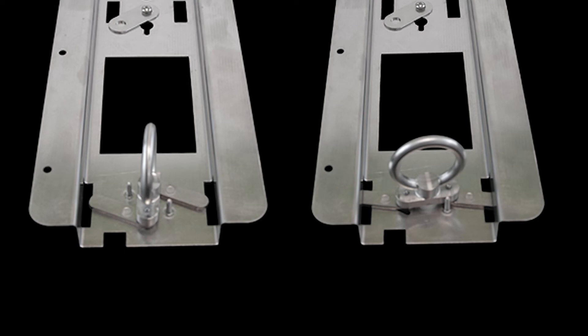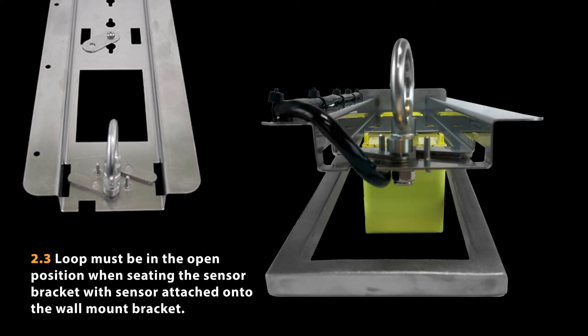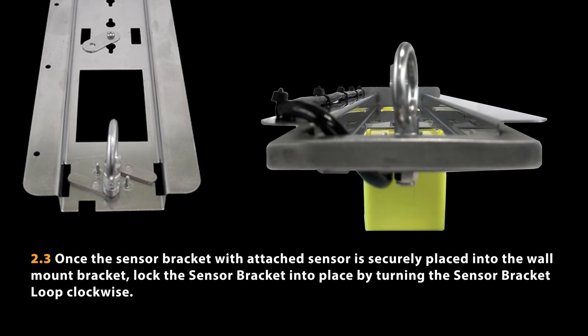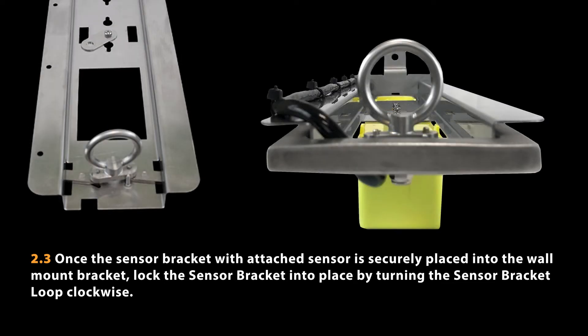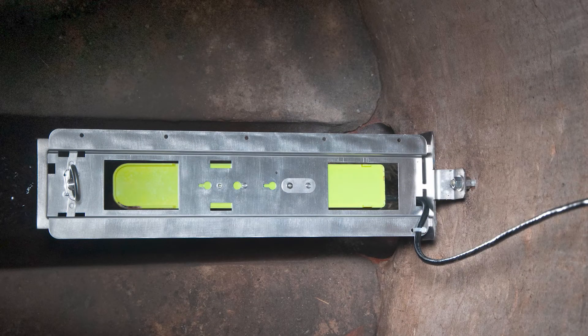The loop on the sensor bracket has two positions: opened and closed. The loop must be in the open position when seating the sensor bracket with sensor attached onto the wall mount bracket. Once the sensor is attached and cable tied to the bracket, lock the sensor bracket into place by turning the sensor bracket loop clockwise. The sensor is now securely installed on the manhole wall.